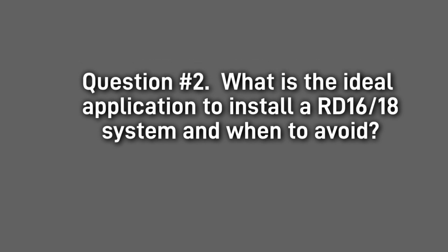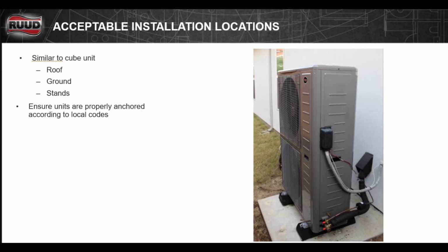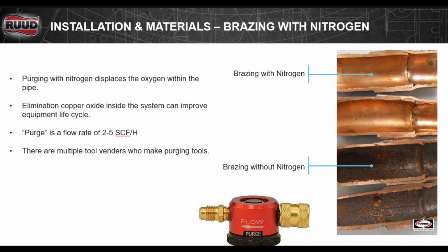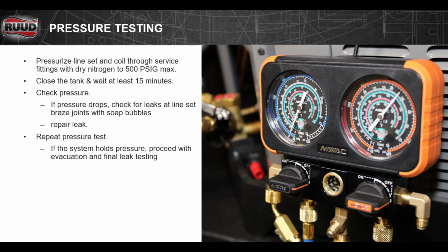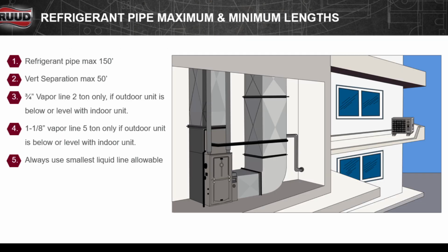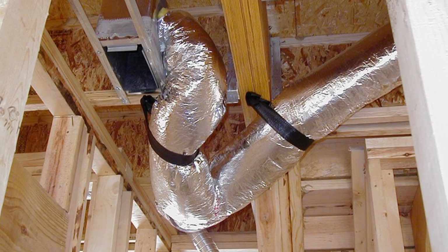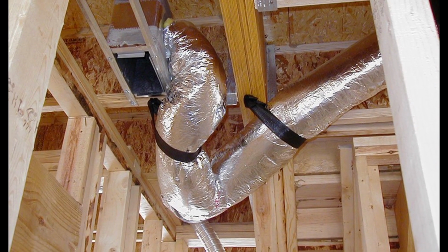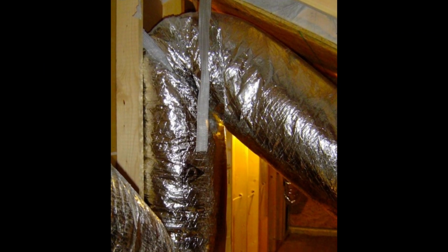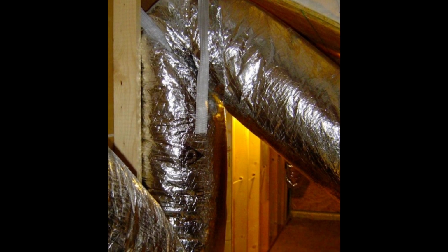Question number 2. What is the ideal application to install an RD16 or RD18 system, and when to avoid? It's important to always be sure to follow local codes and properly anchor your system. Follow best practices by low-flowing nitro, not allowing that cupric oxide to get into the system, and high-pressure testing to avoid any possible leaks after startup. Avoid installing to an existing line set that doesn't meet the line set requirements. In addition to that, poorly designed ductwork is also something that needs to be taken into account. Do not install this system on ductwork that is not designed properly or installed properly.